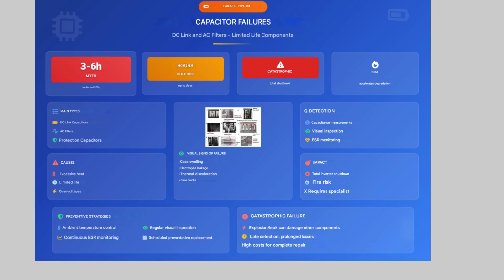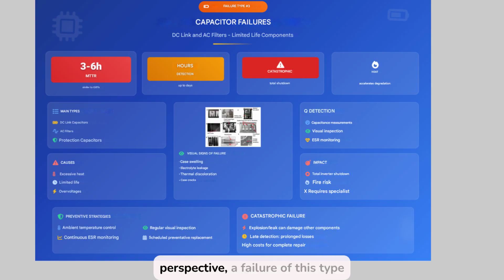From an economic perspective, a failure of this type has several levels of impact. We are not only talking about the cost of the component, but also the energy not produced during the shutdown, the intervention time, and the potential damage to other components such as IGBTs or control boards. Furthermore, if the failure involves a catastrophic leak or explosion, the extent of the damage is multiplied, and repairs may require replacing multiple components and overhauling the entire system. This increases both direct and indirect costs, including penalties for unavailability or breach of PPA contracts.